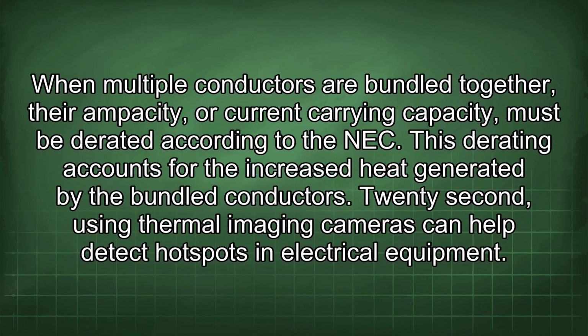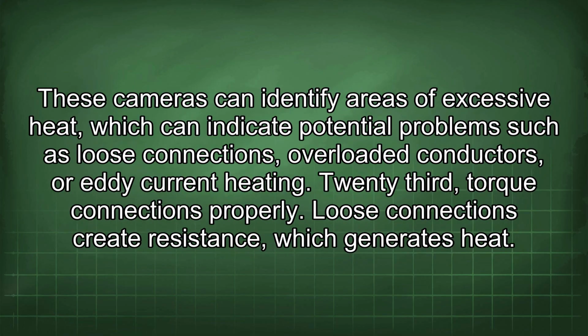When multiple conductors are bundled together, their ampacity, or current carrying capacity, must be derated according to the NEC. This derating accounts for the increased heat generated by the bundled conductors. 22nd, using thermal imaging cameras can help detect hotspots in electrical equipment. These cameras can identify areas of excessive heat, which can indicate potential problems such as loose connections, overloaded conductors, or eddy current heating. 23rd, torque connections properly.